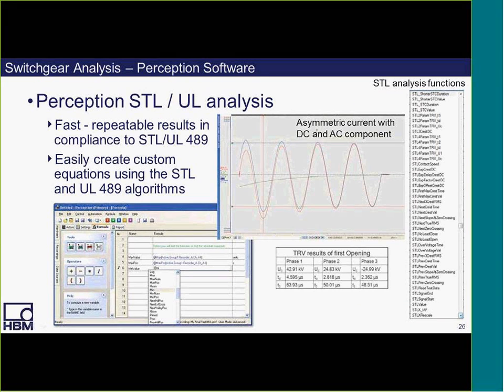Now, the perception software provides complete control, display, and automated analysis and reporting capabilities. Then we have the STL analysis option, which will provide fast and repeatable results in compliance to STL and UL 489 standards. In fact, the analysis includes transient recovery results on single or three-phase systems plus symmetric and asymmetric current. And on the right, you see a list of some of the predefined STL and UL analysis functions in the STL operation manual. Each implemented analysis function is referenced to the relevant paragraph in the STL technical report and provides a complete explanation with diagrams for each analysis function. Now, you can also easily create your own custom analysis equations incorporating any of the STL and UL 489 algorithms.